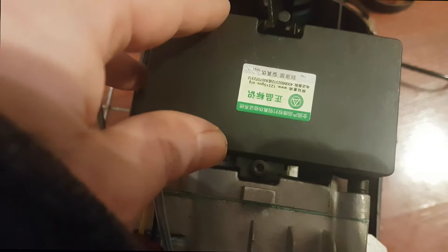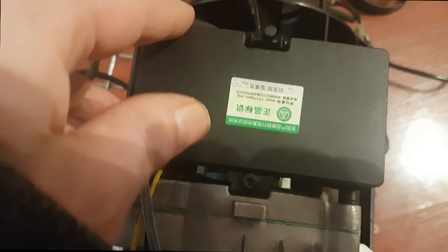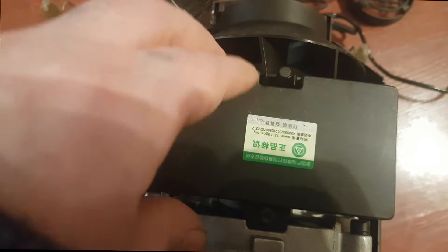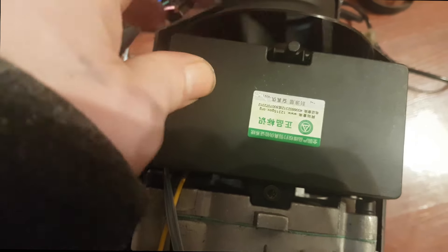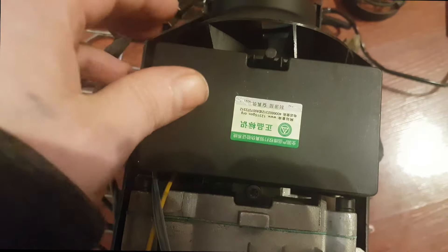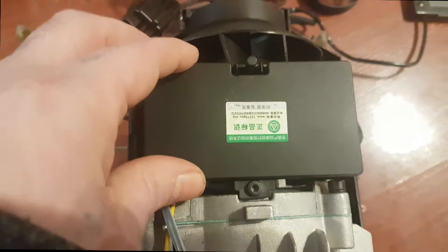Otherwise you might still get the E06 error without the diesel. The E06 — there's no real data on that error. All I know is I was getting it because of the fan. If I don't have any diesel and it's not primed up, I'll get that E06 error again, so it can mean other things as well. But for my fix, it was just this fan. Alright, that's it for this video — like and subscribe, and that's all.